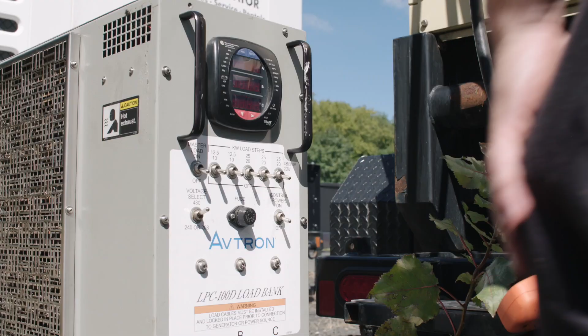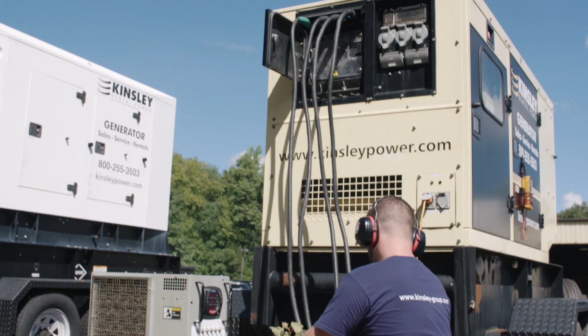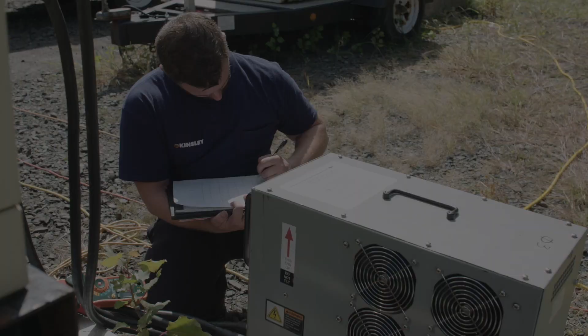A load bank test is where we divert your power from your generator into a separate device called a load bank. A load bank is a resistive device that converts that electricity into heat, because we have to burn it off somewhere. First reason to perform a load bank is to know what that generator is capable of doing. It sets a benchmark. If that generator says it's a 50 kW, we should be able to load bank it at 50 kW. By doing a load bank, we are monitoring that benchmark as it tails off.